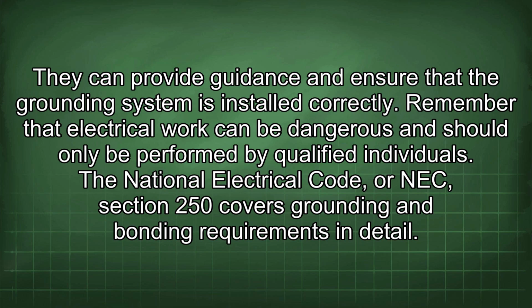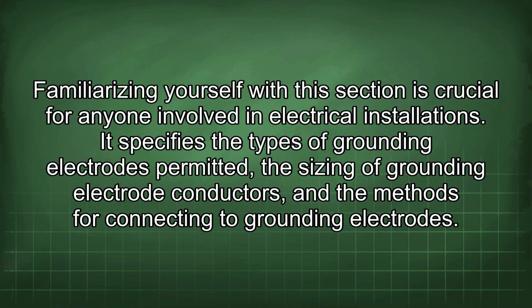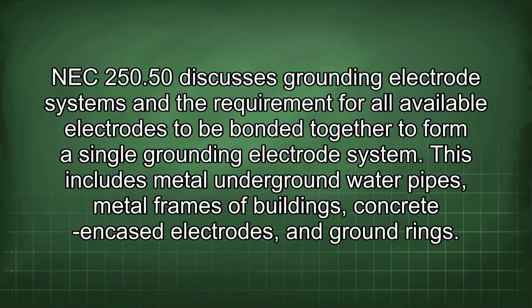The National Electrical Code, or NEC, Section 250 covers grounding and bonding requirements in detail. Familiarizing yourself with this section is crucial for anyone involved in electrical installations. It specifies the types of grounding electrodes permitted, the sizing of grounding electrode conductors, and the methods for connecting to grounding electrodes. NEC 250.50 discusses grounding electrode systems and the requirement for all available electrodes to be bonded together to form a single grounding electrode system.